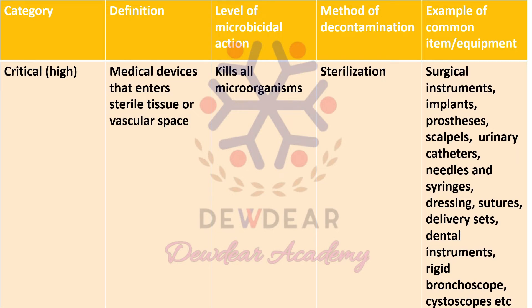The first category is critical, or high. According to this, the medical devices that enter the sterile tissue or vascular spaces are included in the critical category. The level of microbicidal action required here is to kill all the microorganisms, and so sterilization is needed as the method of decontamination for critical devices.